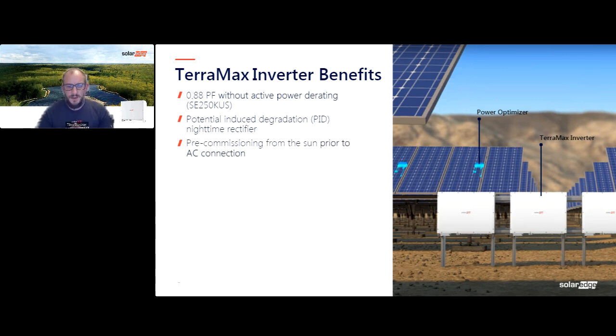The next benefit is we offer the ability to pre-commission from the sun, so we do not require AC interconnection in order to power on the inverter. Our optimizers, when they are first turning on, or when they are not talking and not signaling to the inverter to turn on, output 1 volt per optimizer. So if you have 30 optimizers out in the array, you're going to get 30 volts in that example. And that 30 volts is enough to power our comms board and turn on the communication board, allowing you, the customer, to pre-commission your inverter without requiring AC.